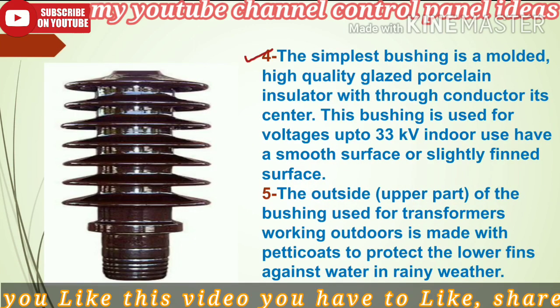Point 4, the simplest bushing is a molded high quality glazed porcelain insulator with a conductor throughout its center. This bushing is used for voltages up to 33 kV indoor. It has a smooth surface or a slightly finned surface.